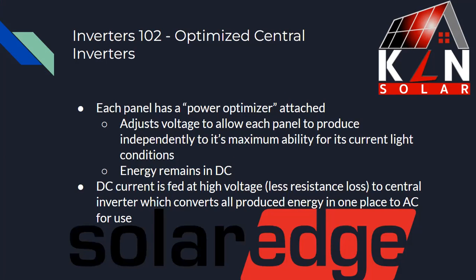What are optimized central inverters? Each panel has a power optimizer attached to it rather than an inverter. What these do is adjust the voltage to allow each panel to produce independently using a concept called maximum power point tracking. The energy remains in DC from the panel level and is fed at a high voltage, where there's less resistance loss, to the central inverter, which converts all the energy produced in one place to AC. Most commonly with these, you'll see SolarEdge as the brand.